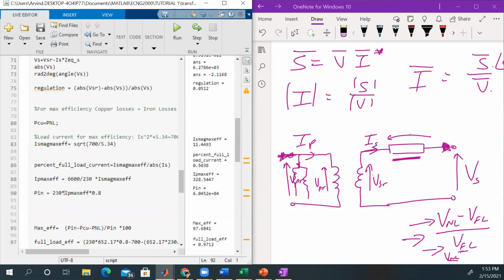To get the input power, we refer this current to the primary, assuming the power factor is the same. So we refer the magnitude to the primary by multiplying by the turns ratio. Since we're going from secondary to primary, the primary is on the denominator. Then to find input power, we take V magnitude multiplied by I magnitude multiplied by the power factor.